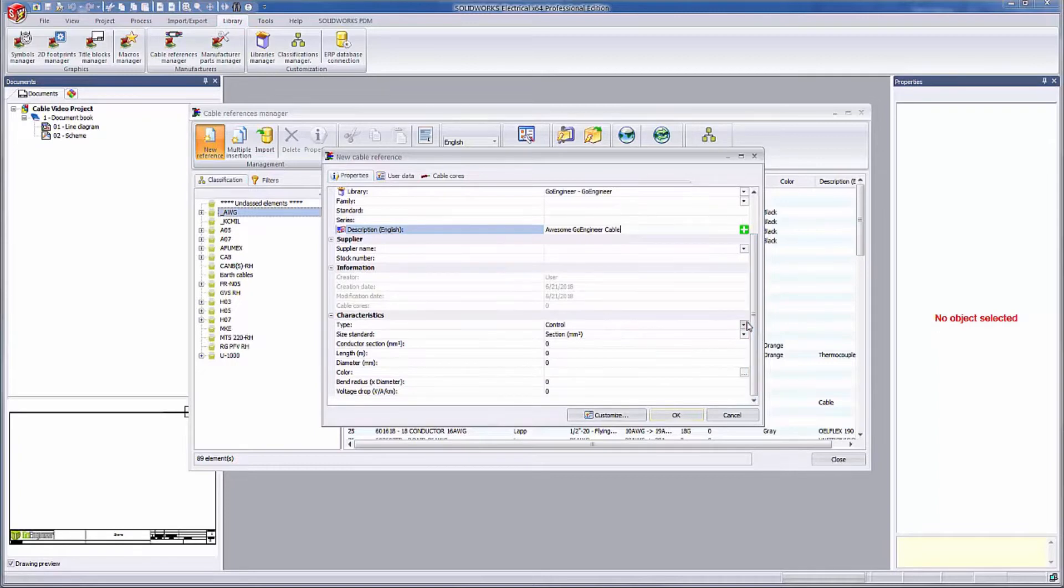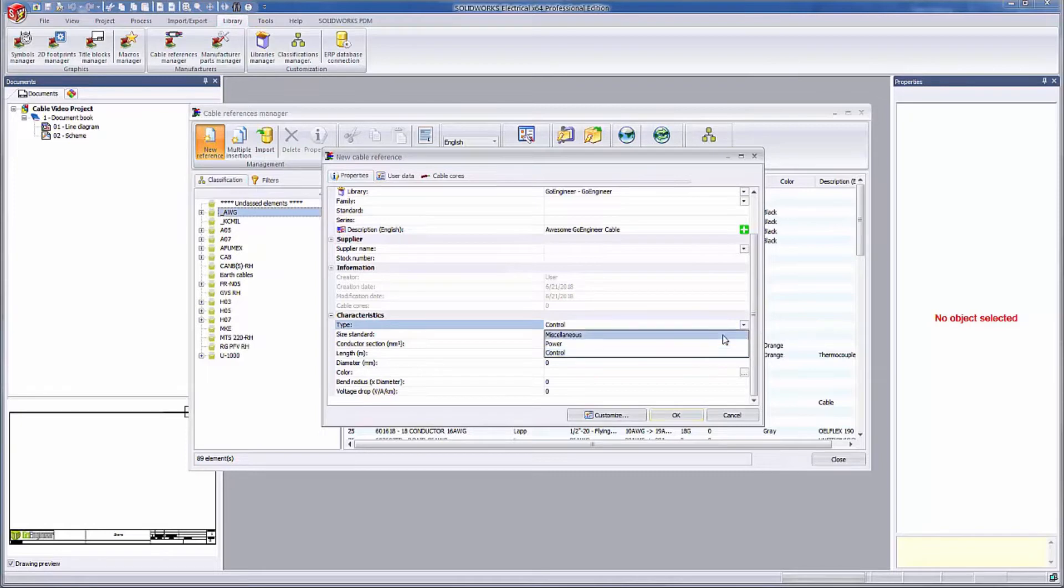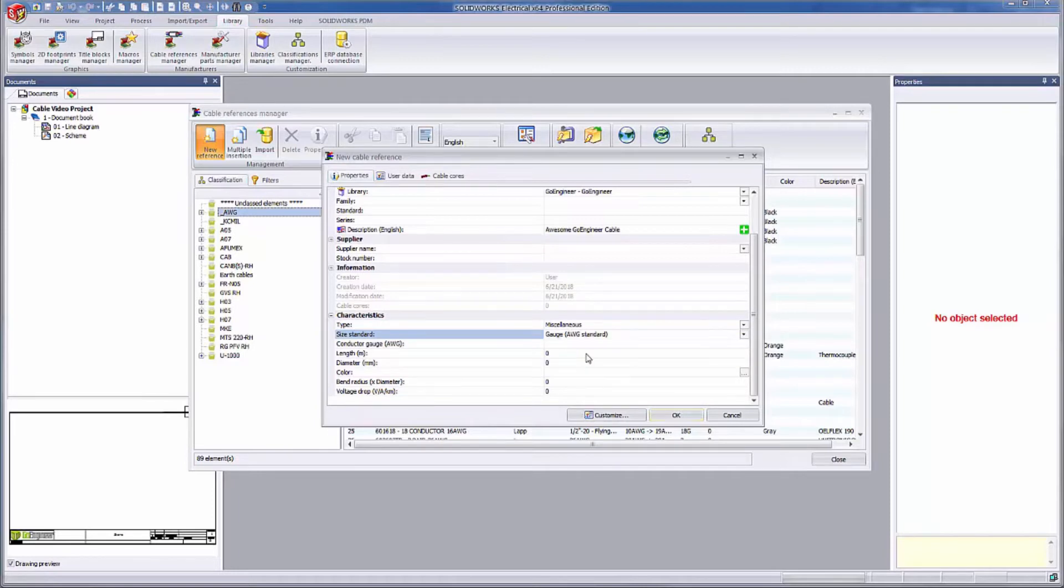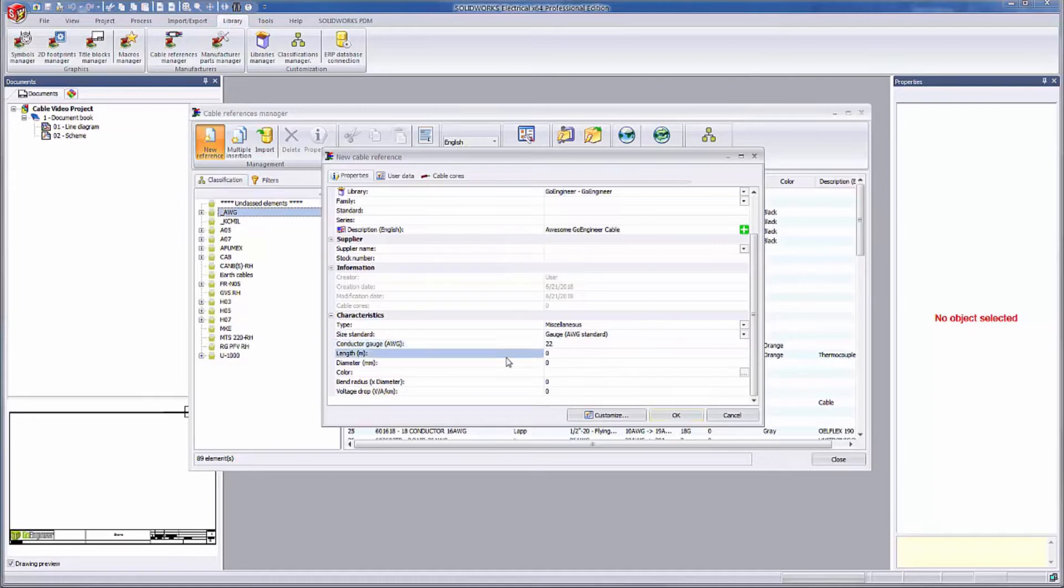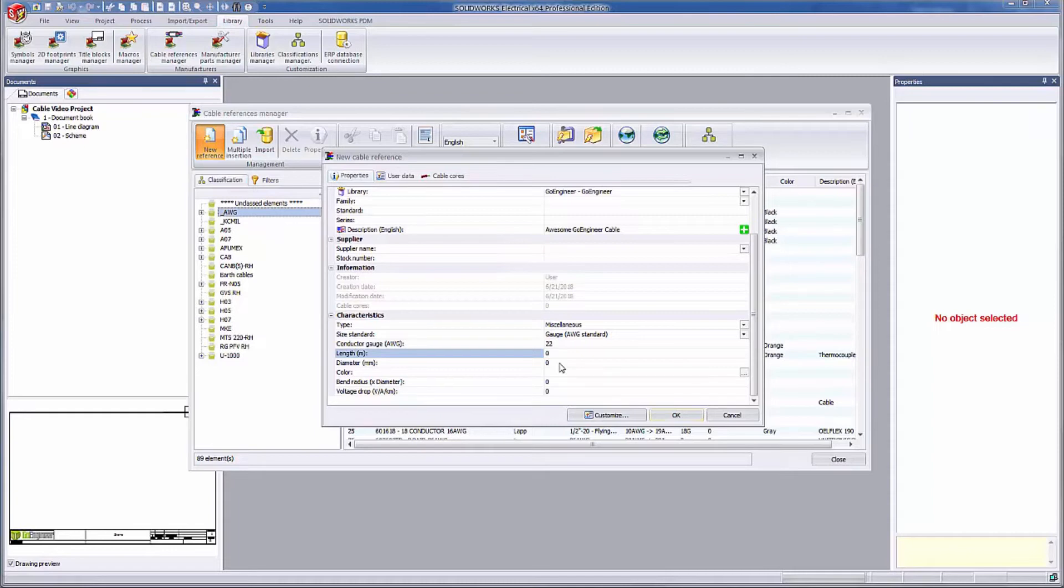I'm jumping down into the characteristics section. Here you can define some of the more physical properties of the cable. When you are defining the conductor gauge, remember that the size standard dropdown provides the units for the gauge. The length field can be filled out manually, but since I have the SolidWorks Electrical 3D add-in, this field will populate after I use it in a project and route the cable in 3D. The diameter field will be used to determine the 3D routed diameter of the cable. I'm just going to say that this cable is going to have a diameter of 4 millimeters.